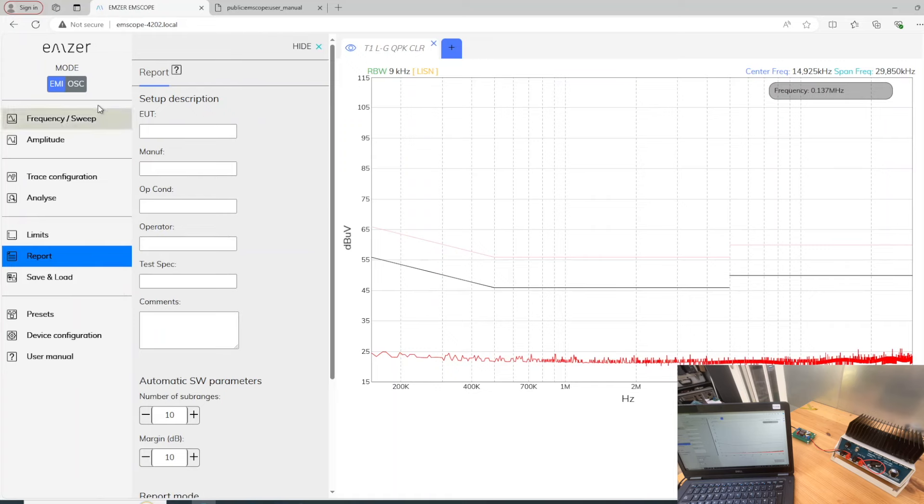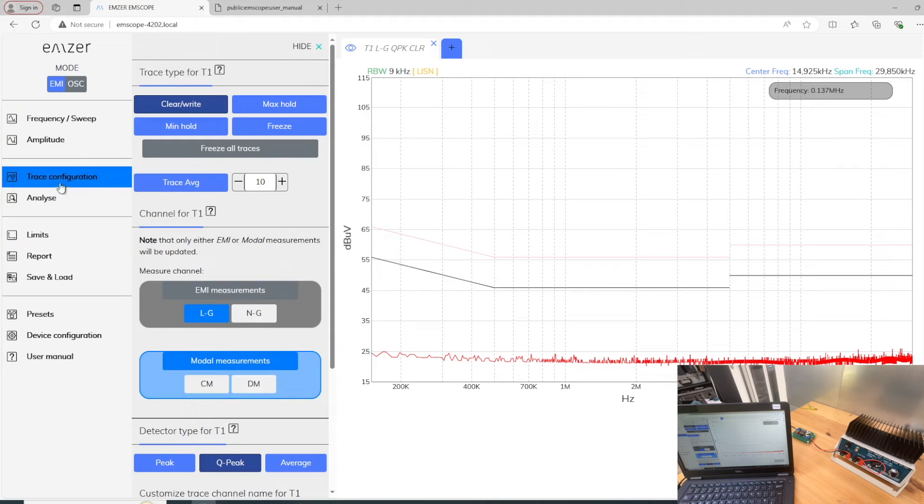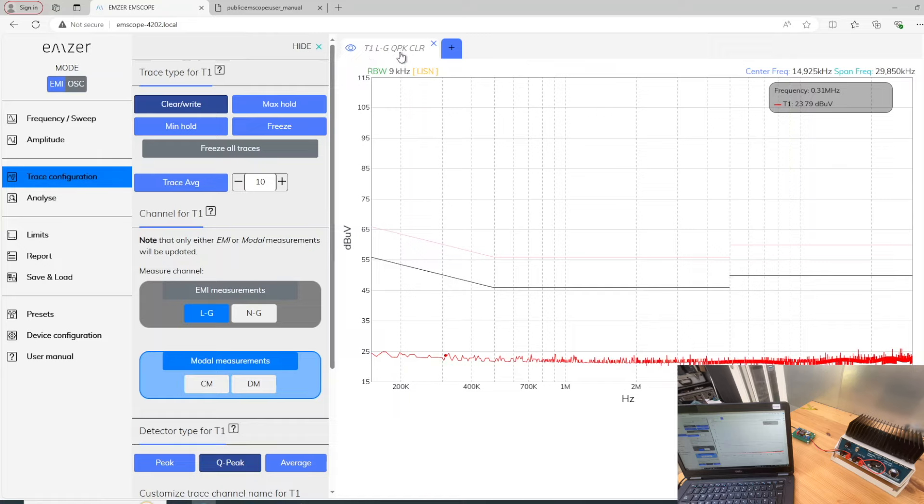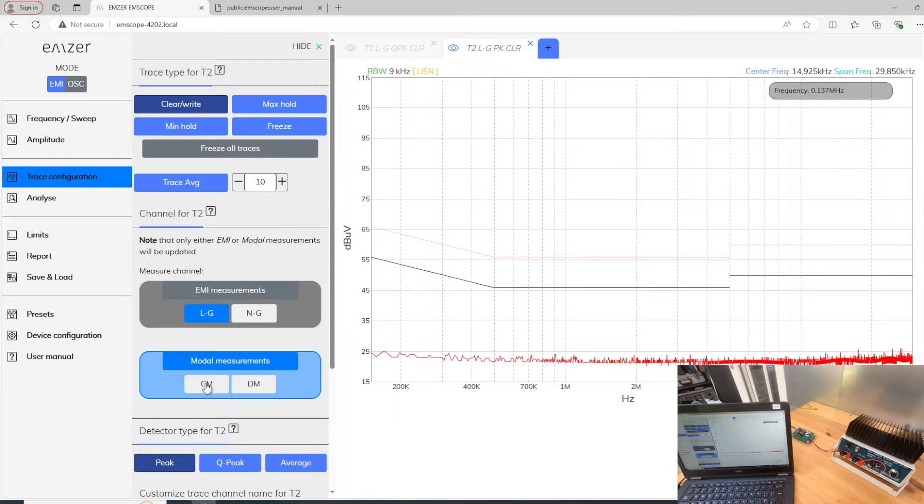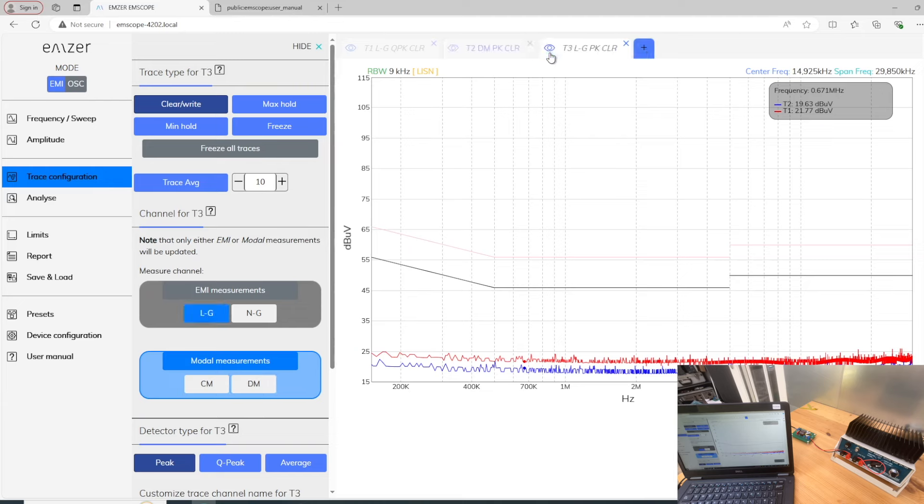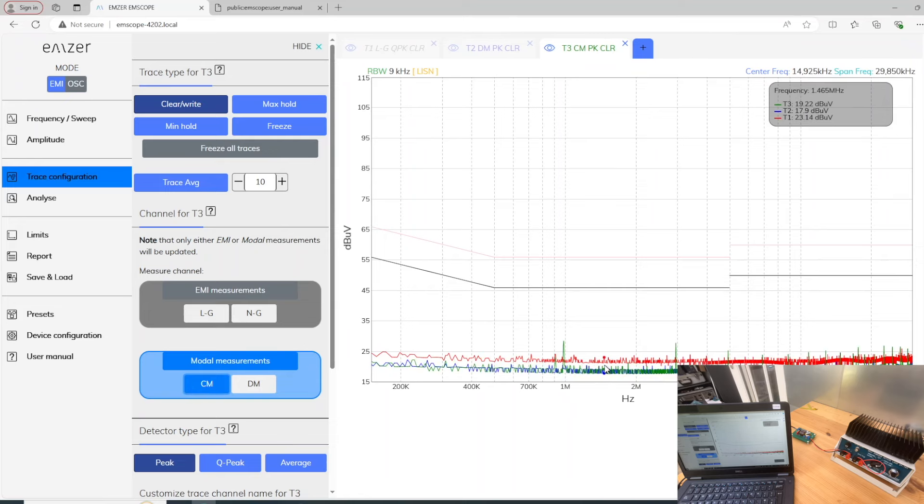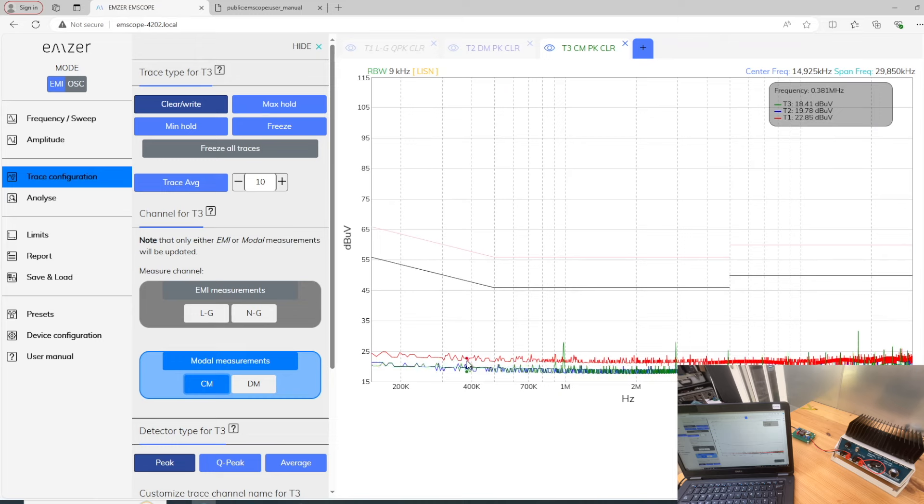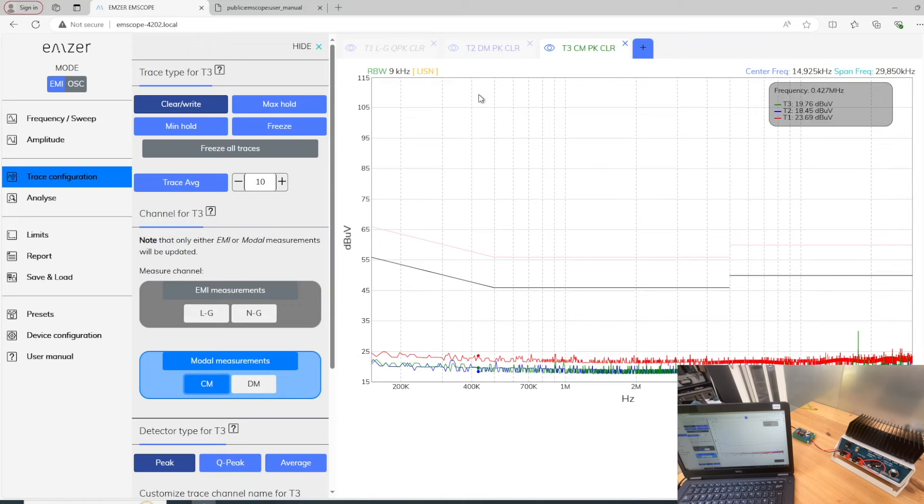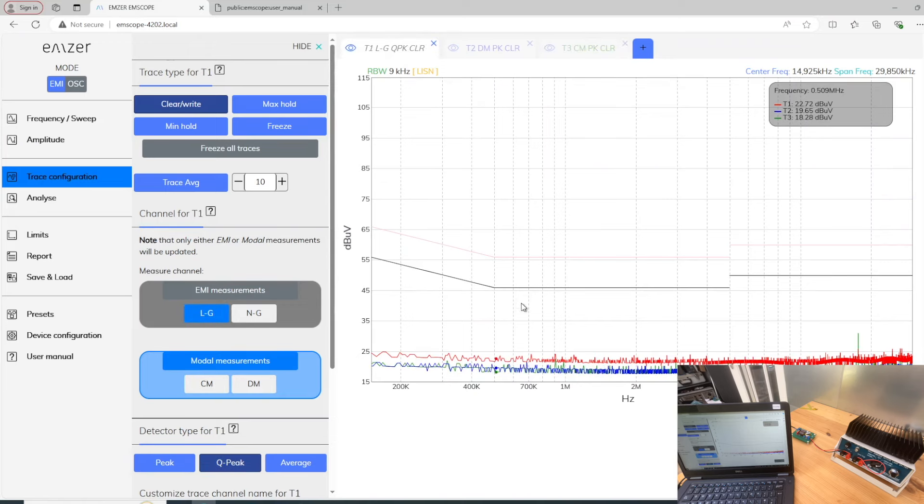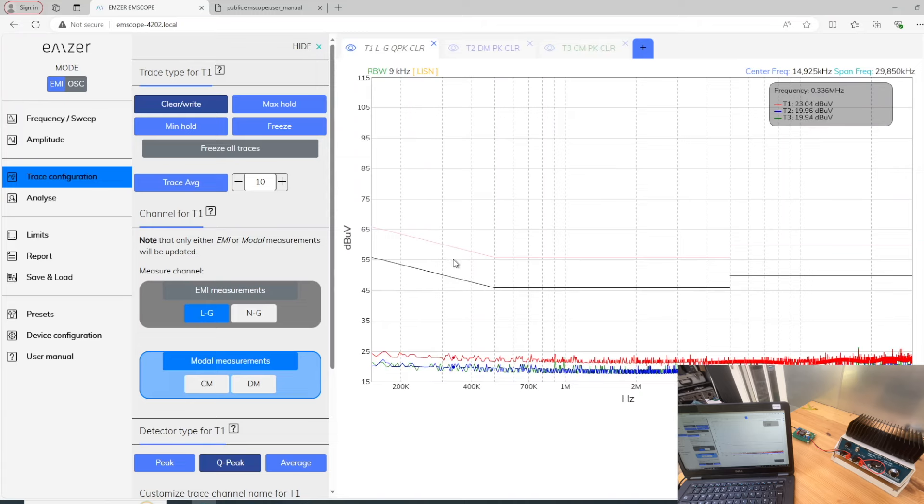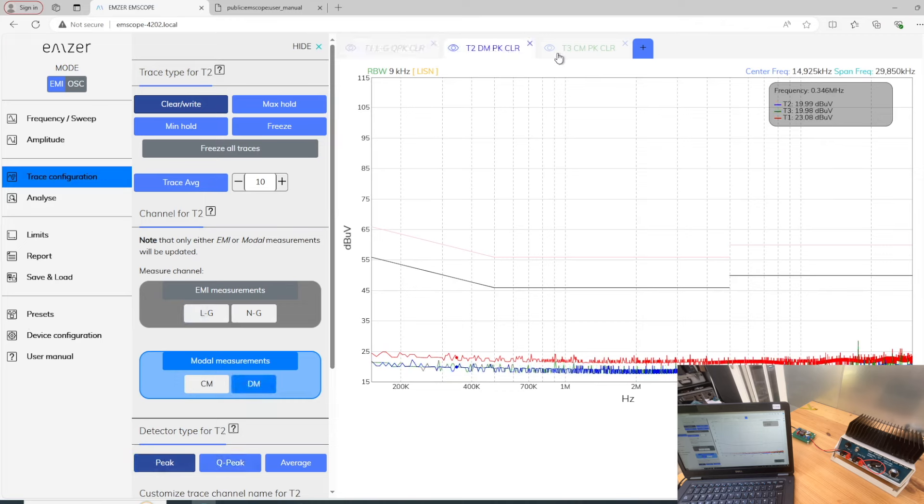Go to trace configuration. Currently trace one we set as measure live quasi peak clear. You can add more. Click trace two, then you can do a modal measurement and measure DM. Click trace three, then you can also look at the common mode. So here we have three traces showing in one graph. You can see that currently it's just measuring the ambience. Once we power the unit up we should be able to see the quasi peak results scanning results of this unit, and I should also be able to see the differential mode and common mode separation. That's one of the unique selling points of this analyzer.